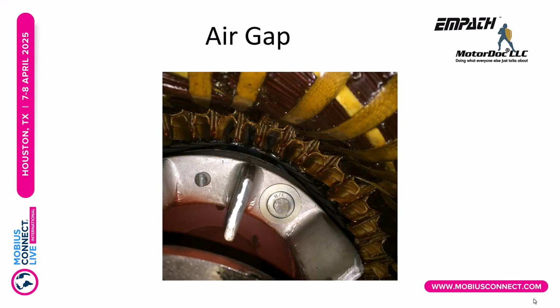But in electrical signature analysis, we go quite direct. The space between the rotor and the stator is called the air gap. That's where the magnetic field goes, and that is the transducer, just like an accelerometer that you would place on the outside of the machine, except this is a very direct measurement. As a matter of fact, not only is it direct, it's relational to the load.